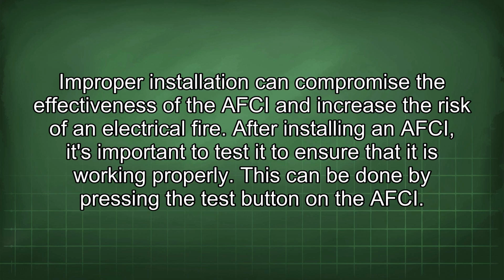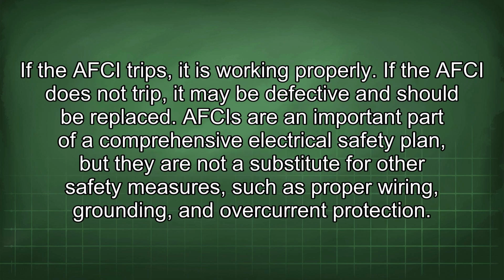After installing an AFCI, it's important to test it to ensure that it is working properly. This can be done by pressing the test button on the AFCI. If the AFCI trips, it is working properly. If the AFCI does not trip, it may be defective and should be replaced. AFCIs are an important part of a comprehensive electrical safety plan, but they are not a substitute for other safety measures, such as proper wiring, grounding, and overcurrent protection.